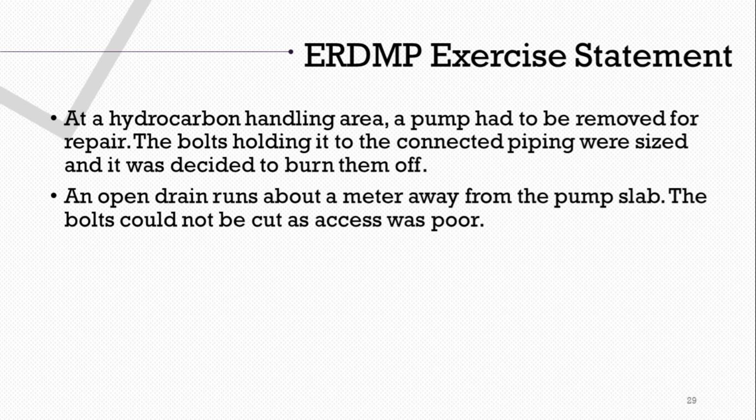Coming to the given exercise statement: at a hydrocarbon handling area, a pump had to be removed for repair. It is decided to burn off the bolts holding the pump, and there is an open drain running a meter away from the pump slab. So there is not very good physical separation from the pump. We need to identify the hazards involved here.